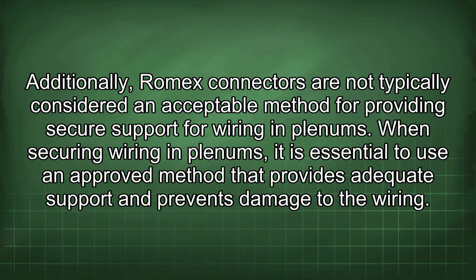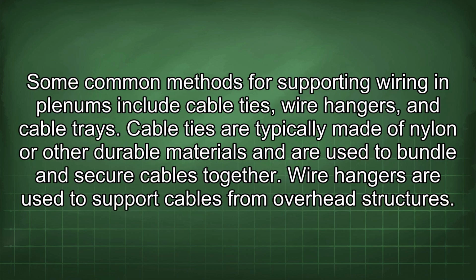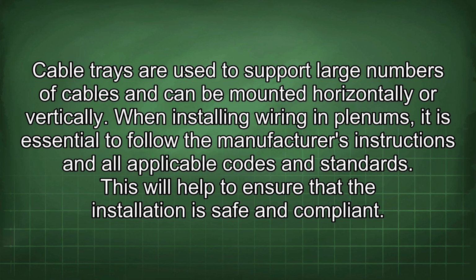Additionally, Romex connectors are not typically considered an acceptable method for providing secure support for wiring in plenums. When securing wiring in plenums, it is essential to use an approved method that provides adequate support and prevents damage to the wiring. Some common methods for supporting wiring in plenums include cable ties, wire hangers, and cable trays. Cable ties are typically made of nylon or other durable materials and are used to bundle and secure cables together. Wire hangers are used to support cables from overhead structures. Cable trays are used to support large numbers of cables and can be mounted horizontally or vertically. When installing wiring in plenums, it is essential to follow the manufacturer's instructions and all applicable codes and standards. This will help to ensure that the installation is safe and compliant.